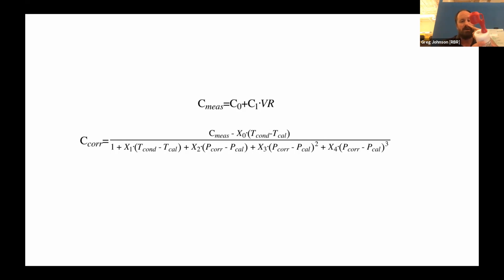Instead, by measuring the cell constant, we can establish that for any shape, and that includes if we have any proximity effects from, let's say, an Argo floating antenna sitting right next to it. However, under pressure, there is still some geometric deformation that occurs, the compression of the cell. And so this pressure dependence factor, the X2, X3, X4, is used to correct the cell for that behavior. Now, it is actually possible, because you can do this with a single point, you can calibrate our conductivity cell at any pressure you like.